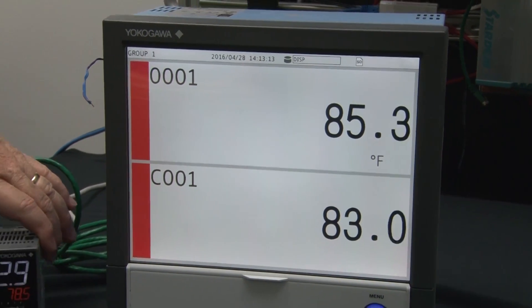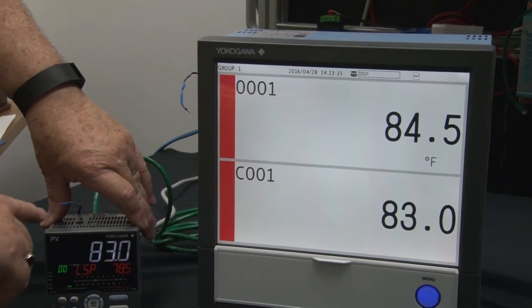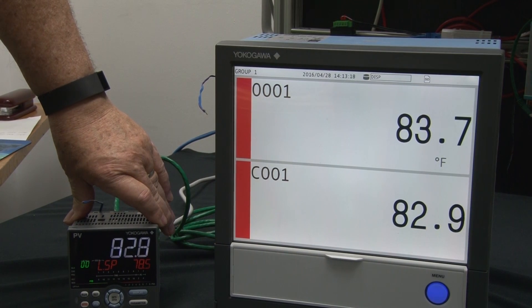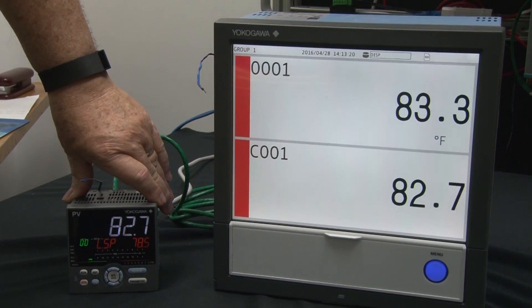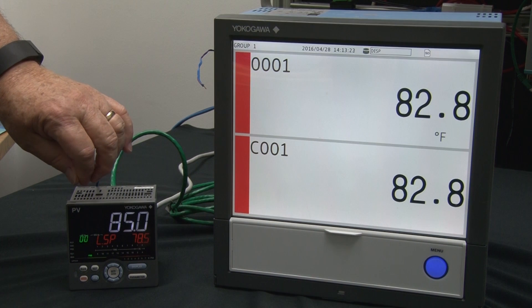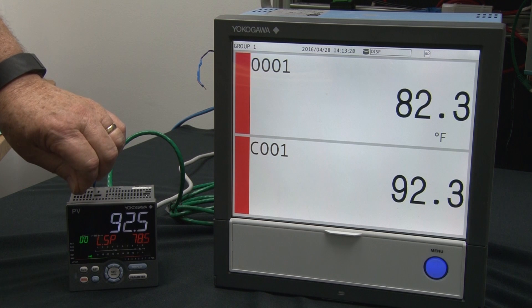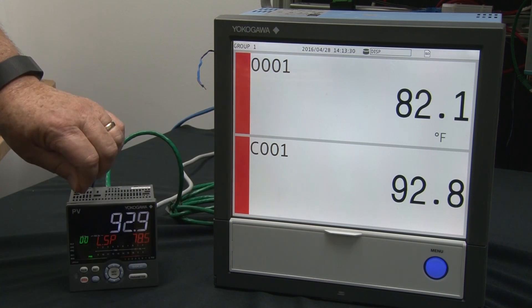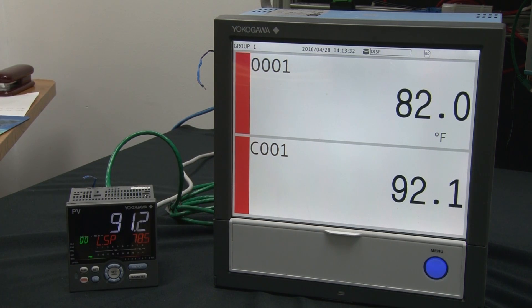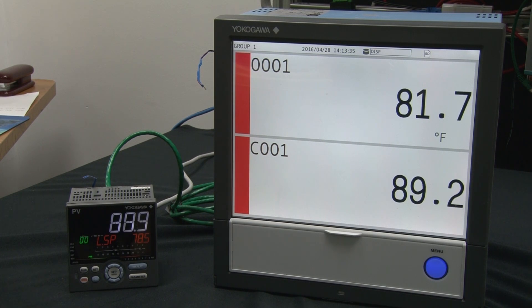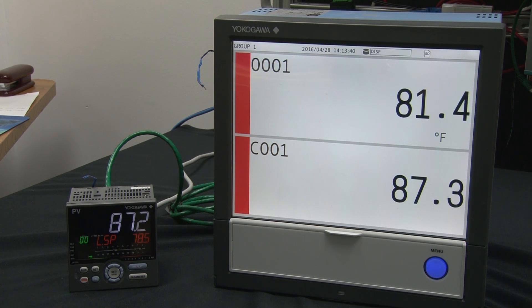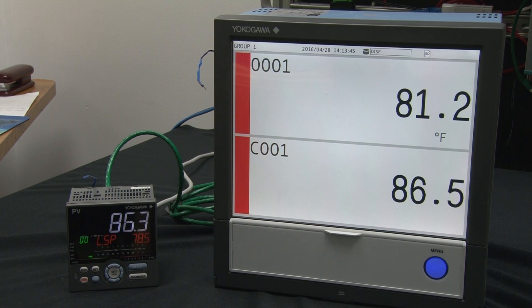Looking at the numbers between the controller and the recorder, they appear fairly similar. Grabbing the thermocouple and driving the temperature up, we're up around 92, and you can see the recorder following along with just a little bit of a time delay because we're only scanning once a second. We've now seen a live demonstration of how to configure and transfer data between two units using Modbus TCP.